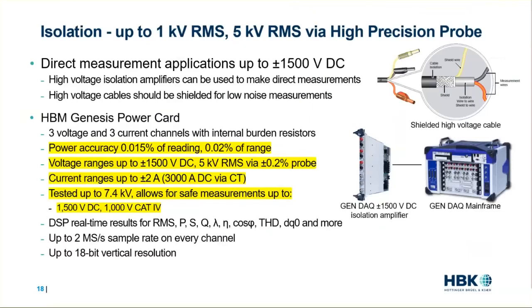So the more phases you have, the more power cards you add to your 2, 3, 4, 7, or 17 slot mainframe. Now, the power card has an accuracy of 0.015% of reading and can measure up to plus minus 1,500 volts DC. Or with an accuracy of plus minus 0.2%, you can measure up to 5 kV RMS with the optional differential probe, as now seen at the bottom right.